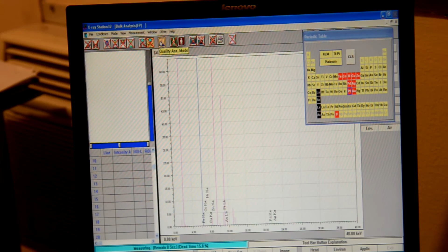I can also adjust the vibration. I can also adjust the peaks, so we can see the growing peaks better and have control over what we're getting, like that. And we see the zinc K-alpha line. We have Au L-beta line. Right now, the end of the line is 29.89 kiloelectron volts and starting from 4.57 kiloelectron volts. It's 0 seconds, and now we have the measurement.